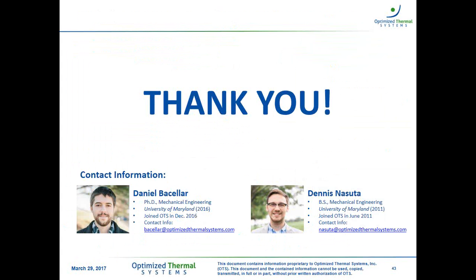The correlations, I don't know that they were summarized in here. I think we only included two-phase heat transfer correlations, but within our software and within the literature, you can find a number of correlations for single-phase heat transfer inside small diameter internally enhanced tubes that would allow you to characterize the performance inside of them, and they would illustrate that the heat transfer is typically higher in an enhanced tube than a smooth tube.